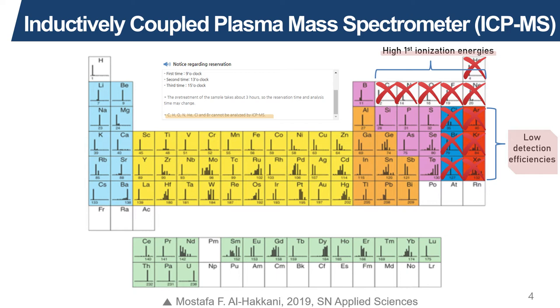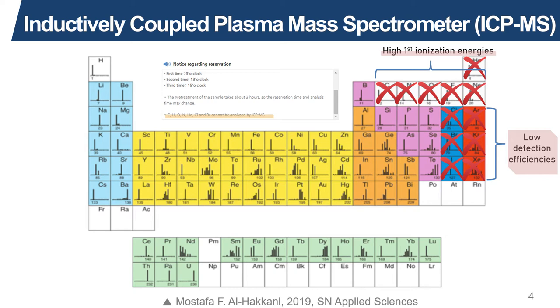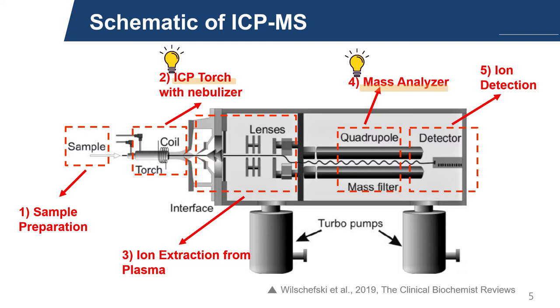Now moving on, we take a closer look into the working principles of the ICP-MS. First, you would of course need to adequately prepare your samples. Let's say you're studying the composition of particulate matter in our atmosphere using the ICP-MS technique. After collecting the specimen, you would first need to dissolve the solid dust particles in strong acid or alkali. This is because dissolved samples not only reduce matrix effects, but also reduce blockage in the nebulizer.